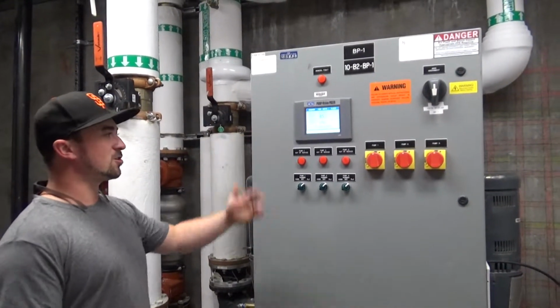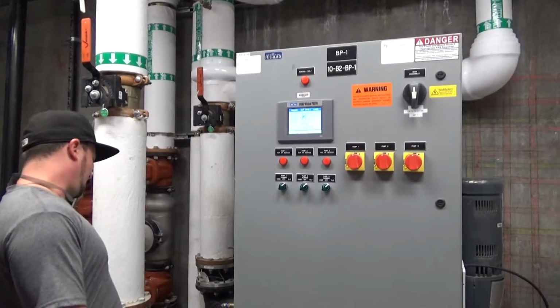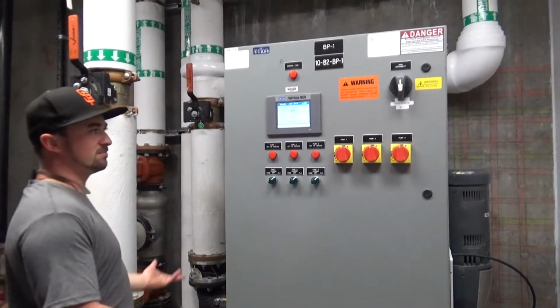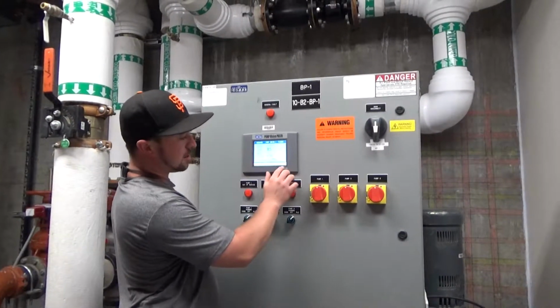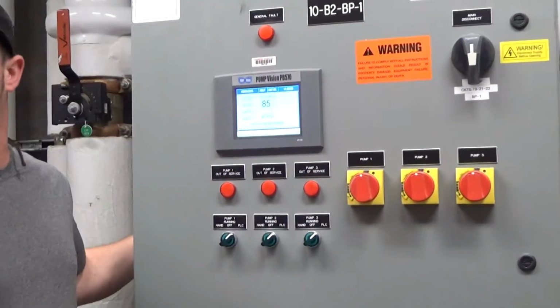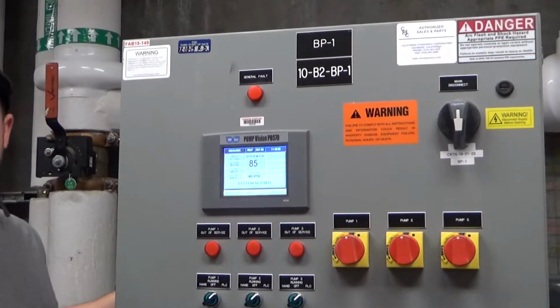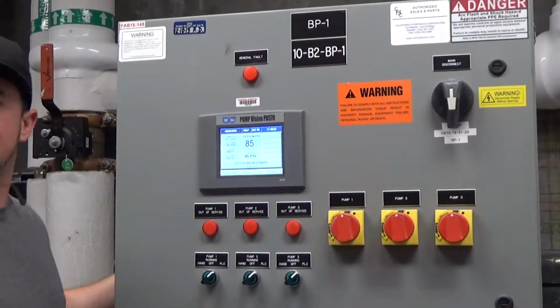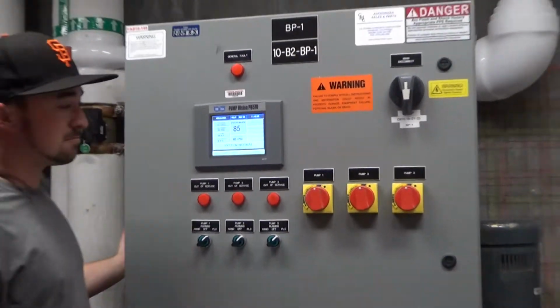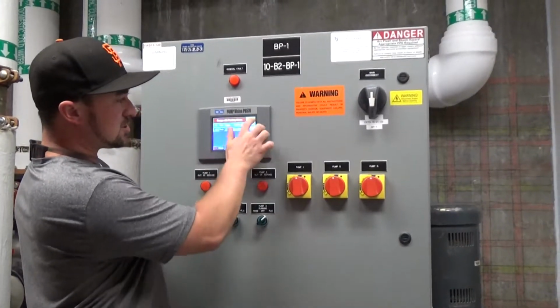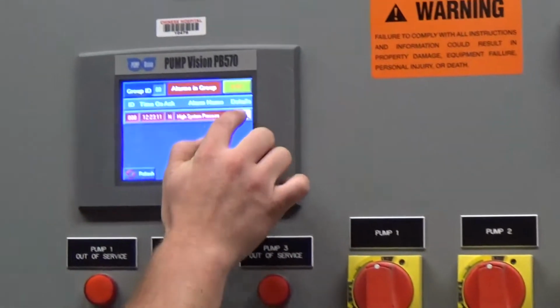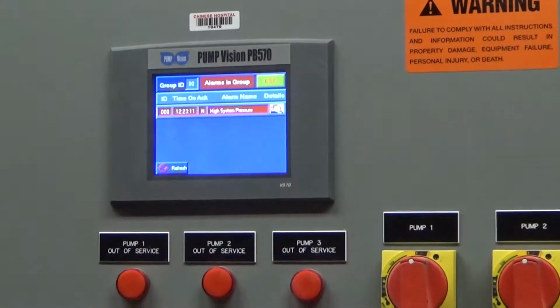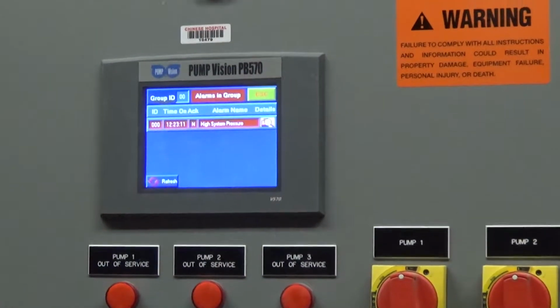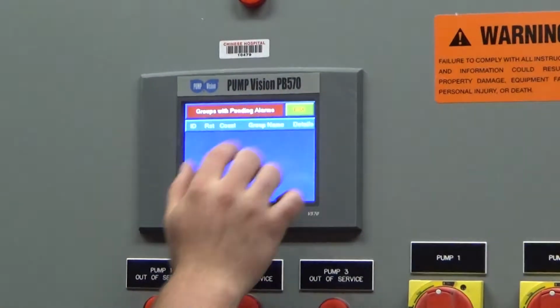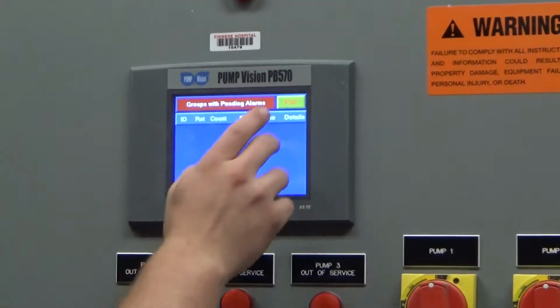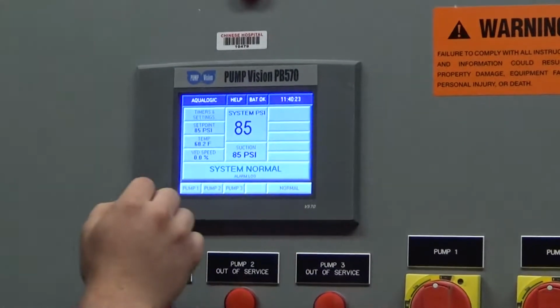The pumps aren't on, so there's not a lot of ways I can really show you guys, but like I said, it's going to light up red right here, and it'll let you know, hey, there's something going on. You're also going to get this lit up. That'll let you know some sort of action needs to be taken, something needs to be looked into, troubleshooting might need to happen. There's also a history, so if you hit the bottom corner where it says normal, hit that little thing. That was the last high system pressure, which is part of our testing. So I'll clear that, so the next time you come up here, if there is an alarm, you know that it's recent. That's how you get to that.